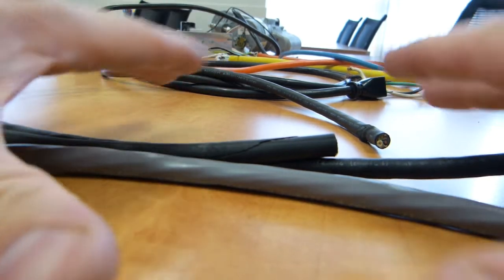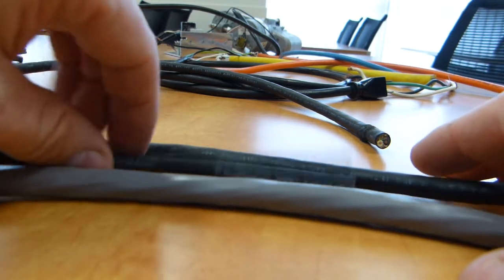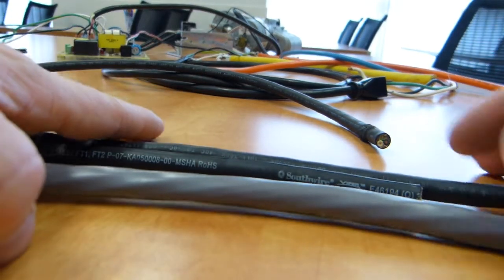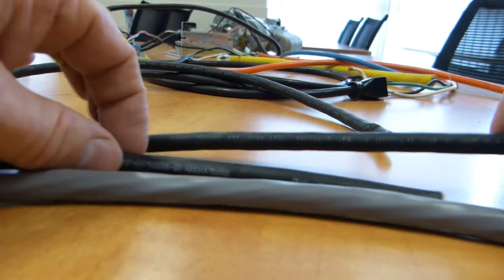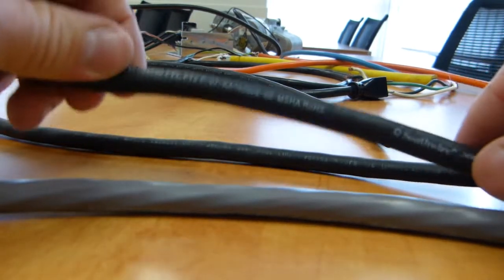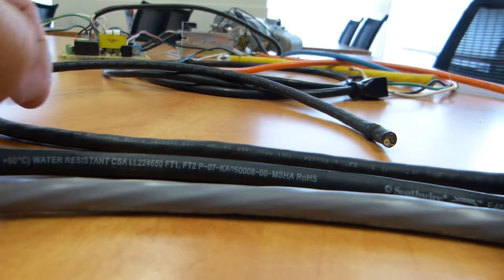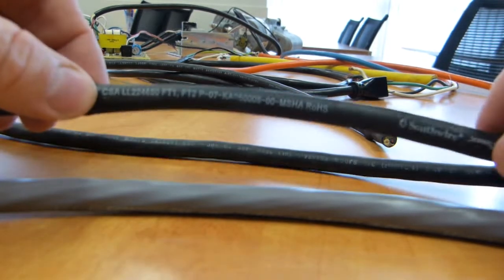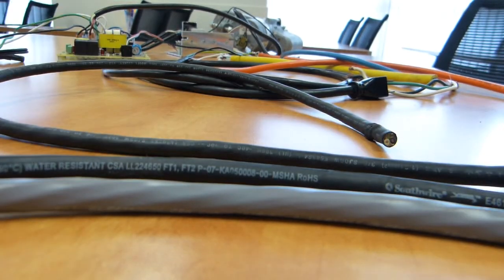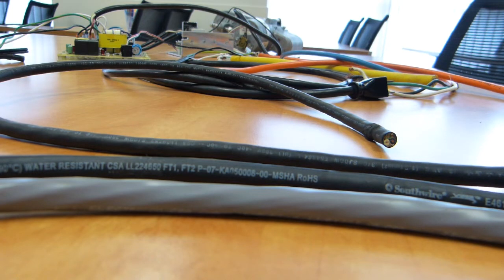In a lower temperature service environment, you can get away with more abuse or using them a little creatively, but often if a 90-degree cable is used in just a 30-degree environment, that just means that it's safer than it was designed for, and there's nothing wrong with extra safety, but just don't be creative with it, trying to feed more amps through it.